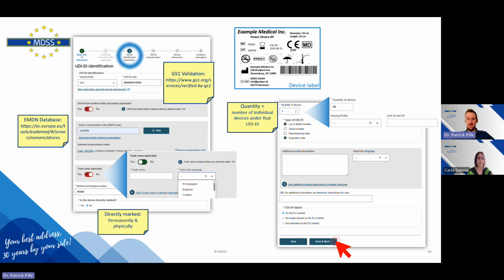You want to make use of the legacy provision. Once the certificate is issued, then the IVDR, MDR registrations have to be done. So you do the legacy registration now, and once the certificate is issued, you register the MDR, IVDR as well. It's a separate registration.